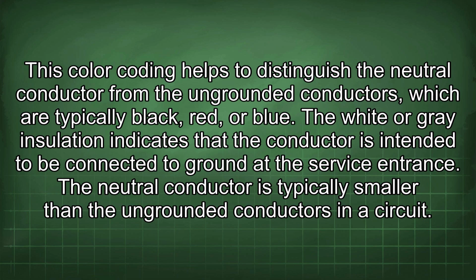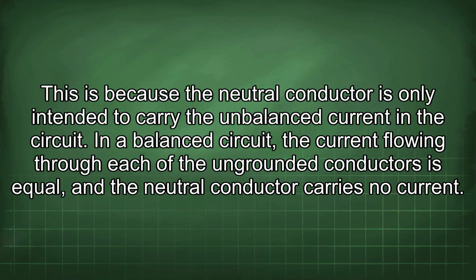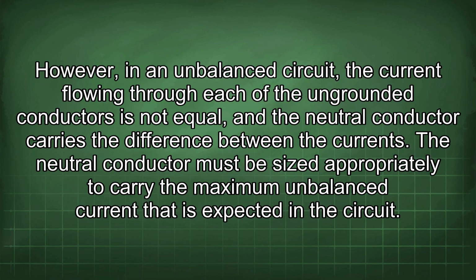The neutral conductor is typically smaller than the ungrounded conductors in a circuit. This is because the neutral conductor is only intended to carry the unbalanced current in the circuit. In a balanced circuit, the current flowing through each of the ungrounded conductors is equal, and the neutral conductor carries no current. However, in an unbalanced circuit, the current flowing through each of the ungrounded conductors is not equal, and the neutral conductor carries the difference between the currents.